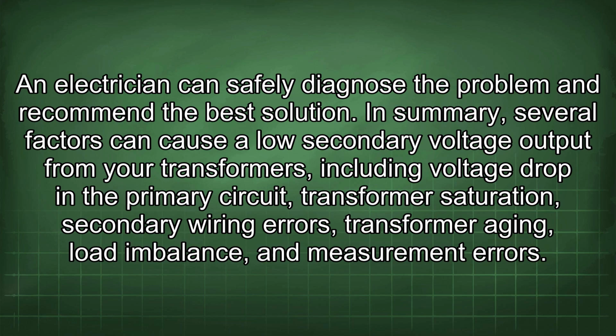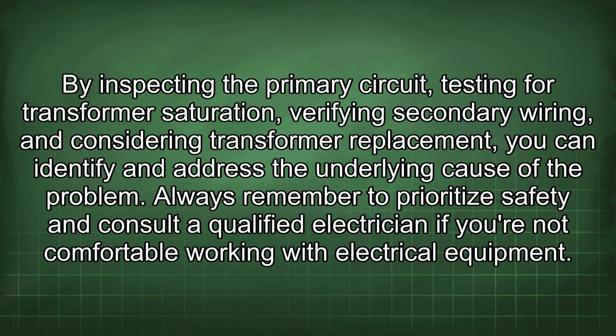In summary, several factors can cause a low secondary voltage output from your transformers, including voltage drop in the primary circuit, transformer saturation, secondary wiring errors, transformer aging, load imbalance, and measurement errors. By inspecting the primary circuit, testing for transformer saturation, verifying secondary wiring, and considering transformer replacement, you can identify and address the underlying cause of the problem.